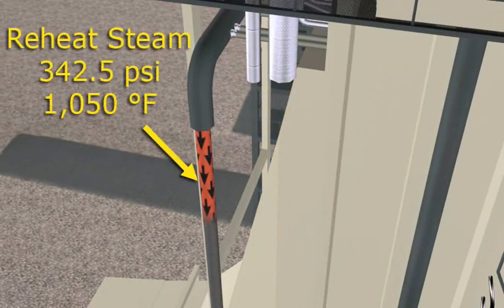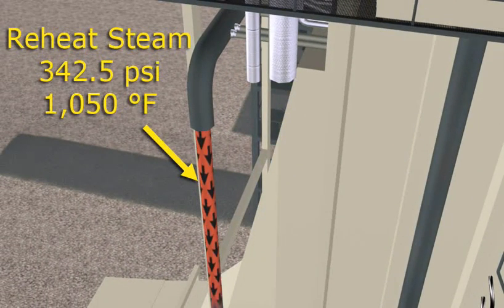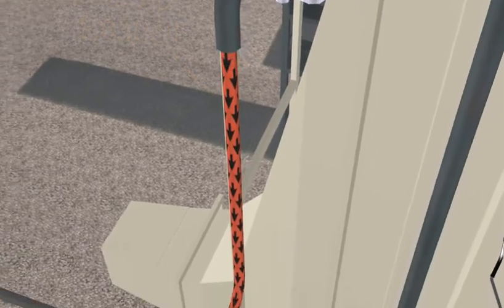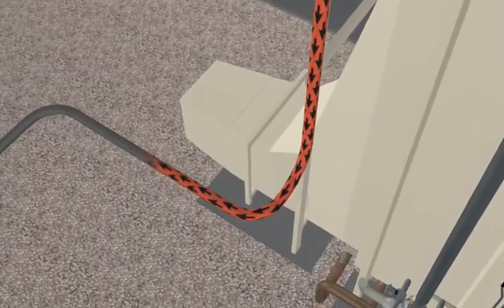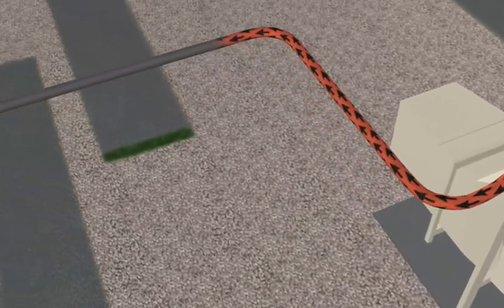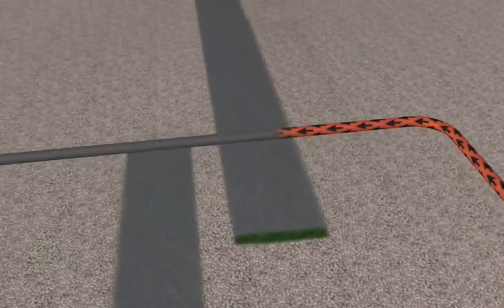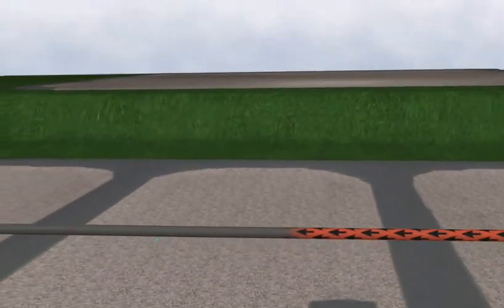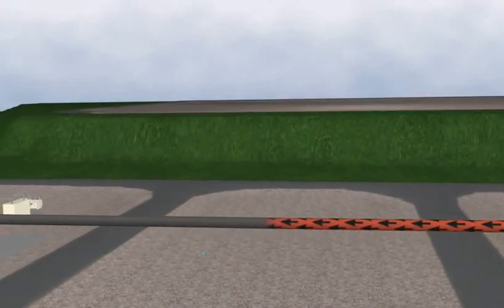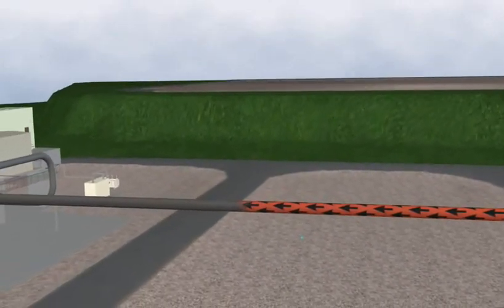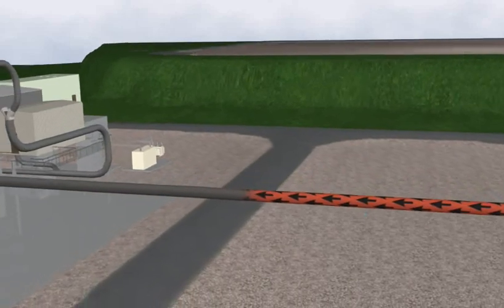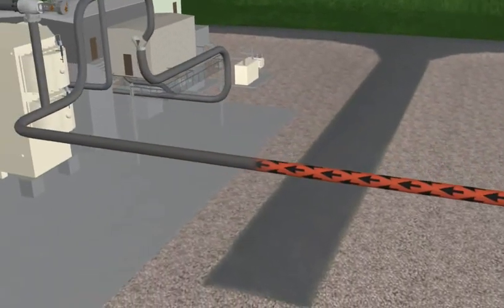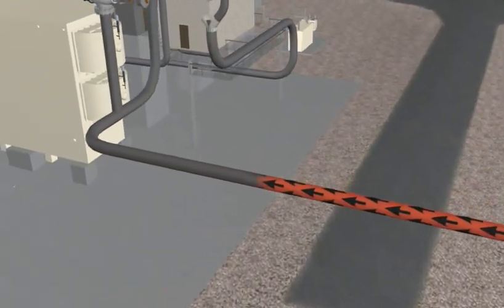Reheat or intermediate pressure steam runs at 342.5 PSI at 1,050 degrees Fahrenheit. Reheat steam may also be referred to as cold reheat for reheat steam returning to the HRSG or hot reheat for reheat steam leaving the HRSG.